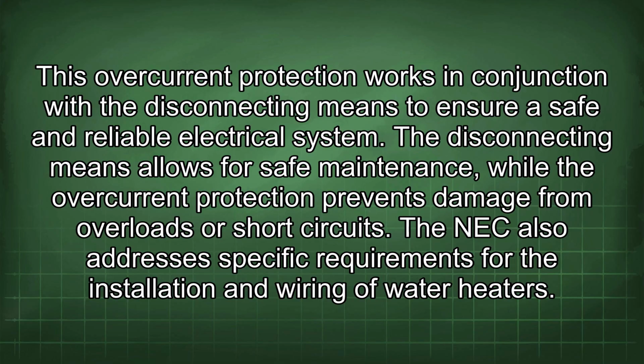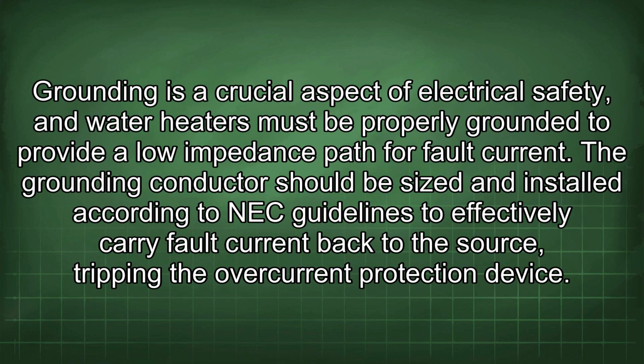The NEC also addresses specific requirements for the installation and wiring of water heaters. Grounding is a crucial aspect of electrical safety, and water heaters must be properly grounded to provide a low impedance path for fault current. The grounding conductor should be sized and installed according to NEC guidelines to effectively carry fault current back to the source, tripping the overcurrent protection device.